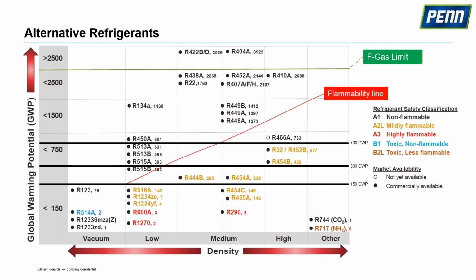You can see that both R454C and R455A are below the 150 GWP limit, whereas R454A is a little higher at 239. But keep in mind that SNAP Rule 25 does include R454A, mainly because it's much higher in efficiency than the other two refrigerants, and it allows for a lower evaporator temperature.